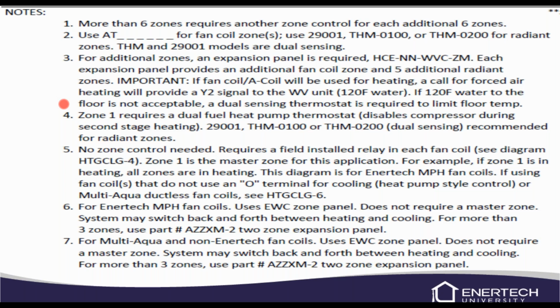The THMs and the 29001, those are all dual sensing. Anytime we have a zone that has forced air and radiant in one zone, we always want to use a dual sensing thermostat. What happens is if you get a forced air call when you have a radiant call, you're going to have a higher temperature leaving the unit than what the radiant floor may want. So if we have a dual sensing with a floor sensor, if that water temperature gets too hot in that radiant floor zone, it'll shut off that radiant floor zone.